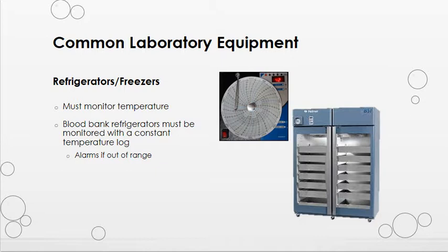Refrigerators and freezers are also found in most departments in the lab. These require temperature to be monitored and logged according to protocol — this may be every 24 hours, 12 hours, 8 hours, etc. Blood bank refrigerators have more stringent guidelines which require temperature to be recorded constantly. The image here shows a temperature monitor that records temperature constantly, with a round piece of paper, and those records must be saved for a certain amount of time per your accrediting agency.